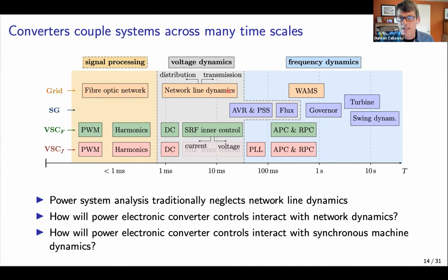Now let's look here: we've got voltage source converters, capital F meaning grid forming, lowercase f meaning grid following. If we think about the timescales of these control loops, the DC side control—think of your battery DC voltage or your PV inverter or PV panel DC voltage—and then the synchronous reference frame inner control, which is on current and voltage, those happen in the 1 to tens of milliseconds timescale, the same as our network line dynamics.